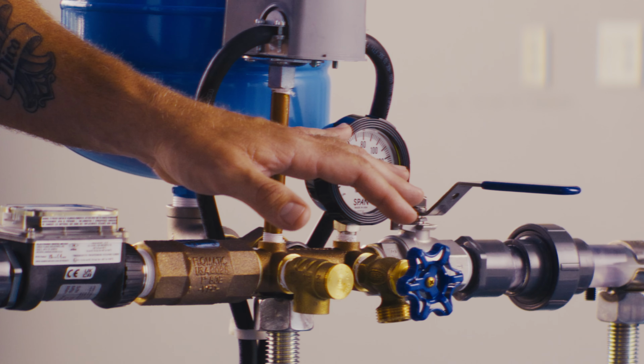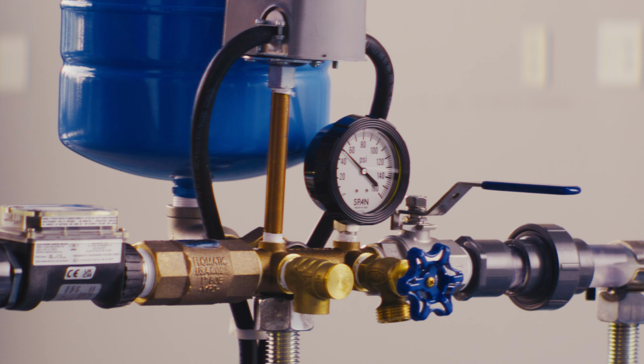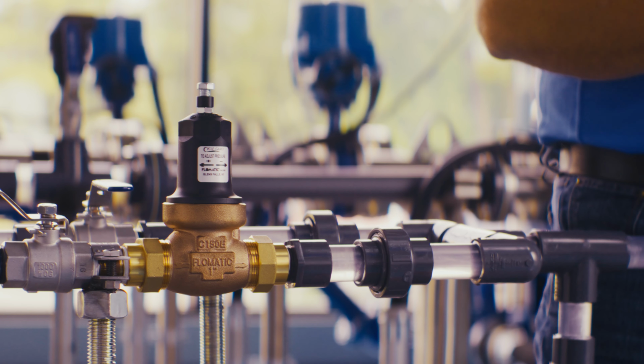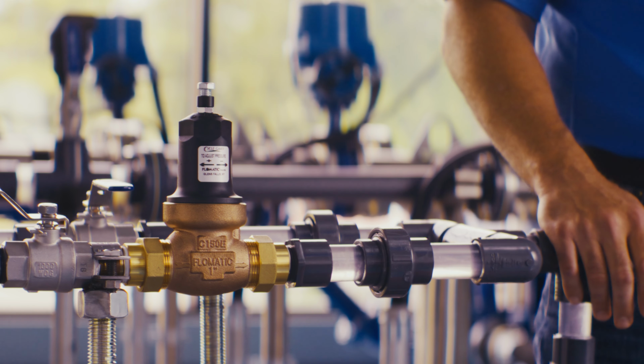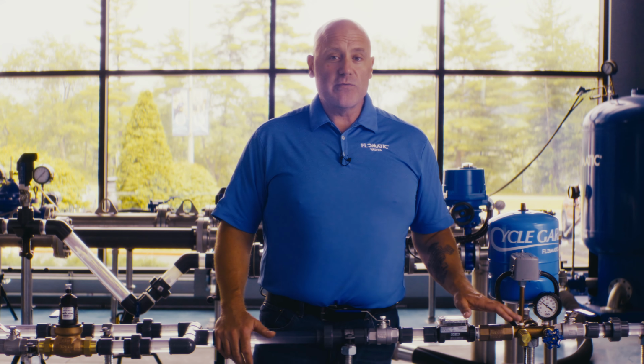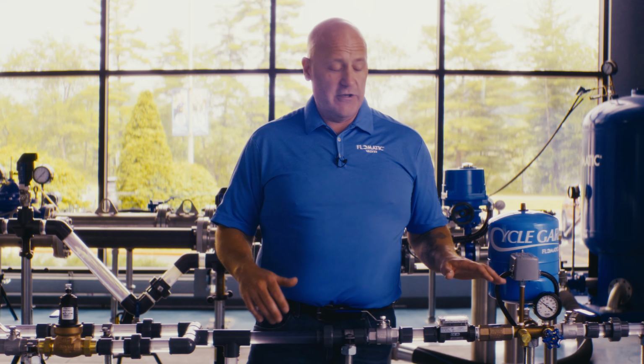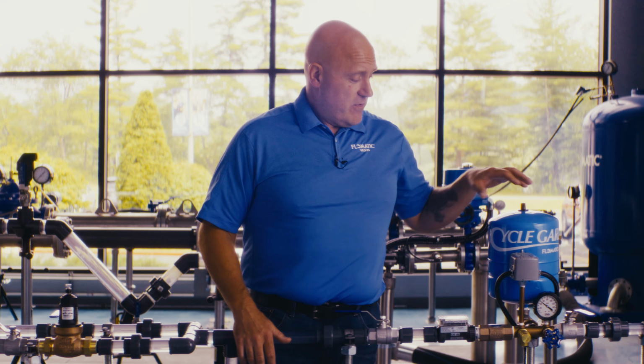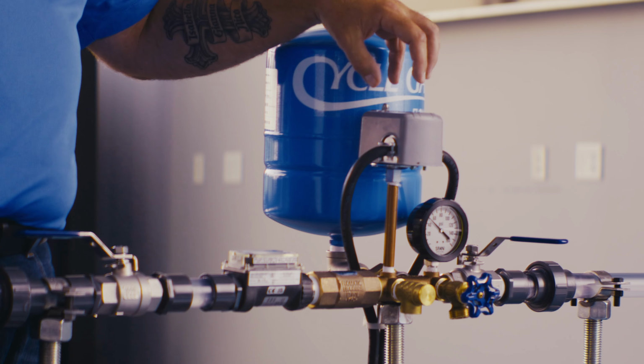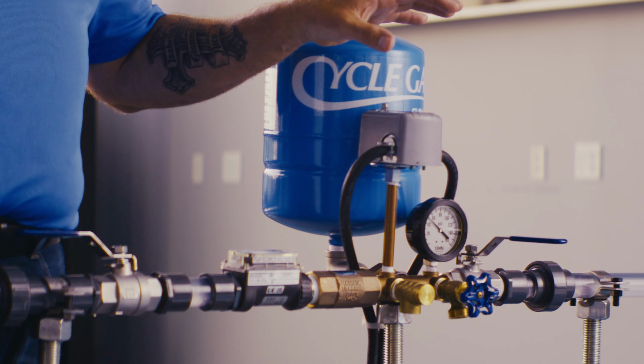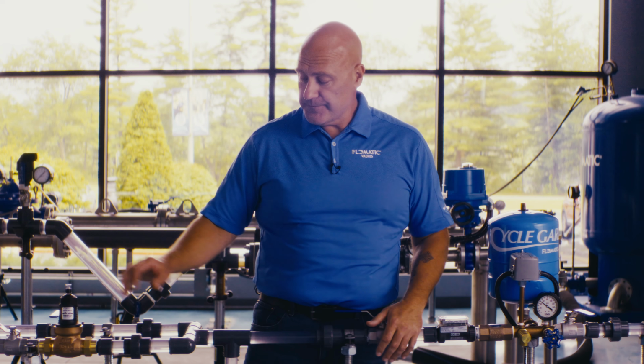We may see a drop in the pressure here from our 50 PSI. Direct acting valves have what's called a fall off, or similar to a head loss. The higher the flow that we are trying to put through this valve will impact the pressure here. So this will need to be taken into consideration when commissioning the system for the first time, dependent upon the size of our tank, the settings on our pressure switch, and the constant pressure required in the household. We need to keep in mind the starts and stops on the motor.